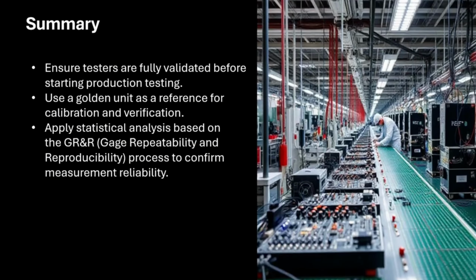As a summary, we want to make sure that our tester is ready before you run the manufacturing test. If the tester, let's say, is not ready, it might over-reject your units and make your yield very bad, or under-reject the units, and that will cause more problems because you think that the unit is tested and ready, it passed when it's not supposed to, and then it's sold to the customer, and then you have to recall. So these are the risks involved when your tester is not ready but you release it to the manufacturing process. You can use golden units as a reference for calibration and verification.